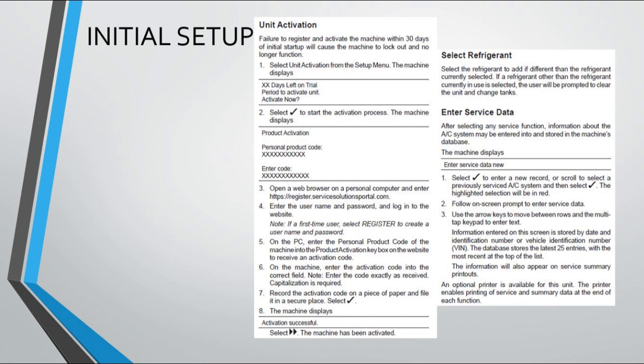Enter service data. After selecting any service function, information about the AC system may be entered into and stored in the machine's database. The machine displays "Enter service data new." 1. Select to enter a new record, or scroll to select a previously serviced AC system and then select. The highlighted selection will be in red. 2. Follow on-screen prompts to enter service data. 3. Use the arrow keys to move between rows and the multi-tap keypad to enter text.